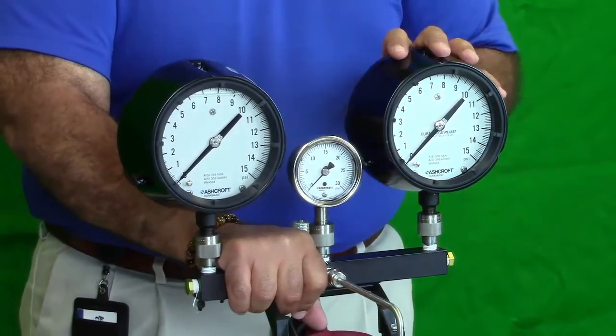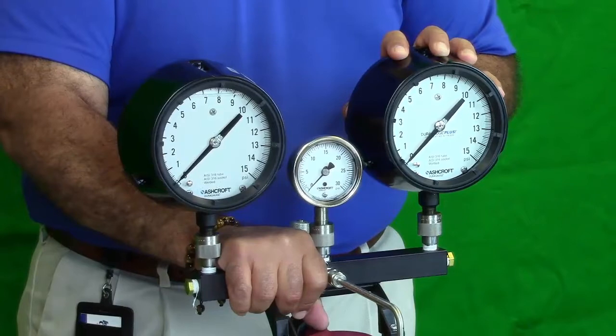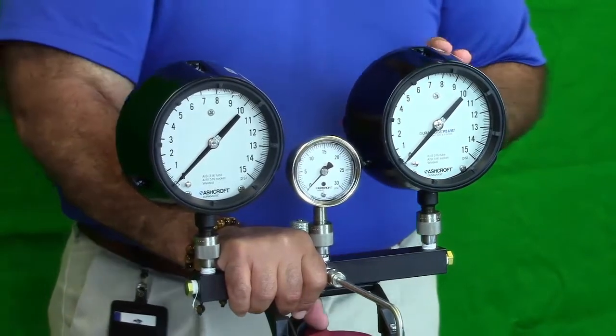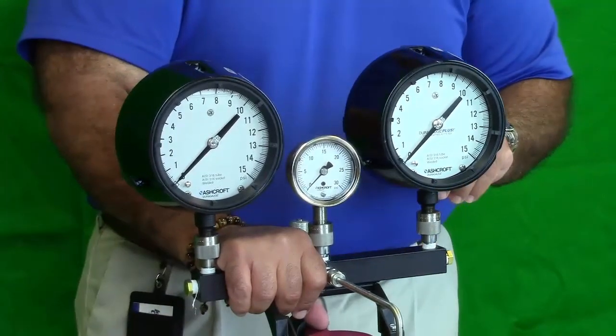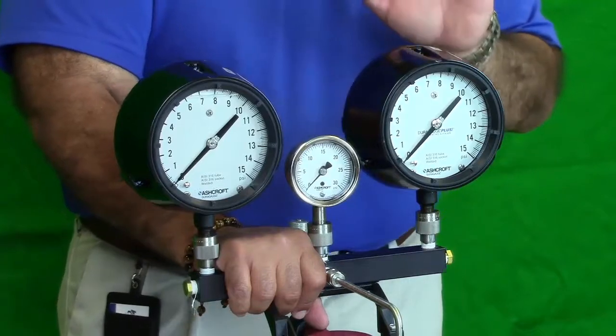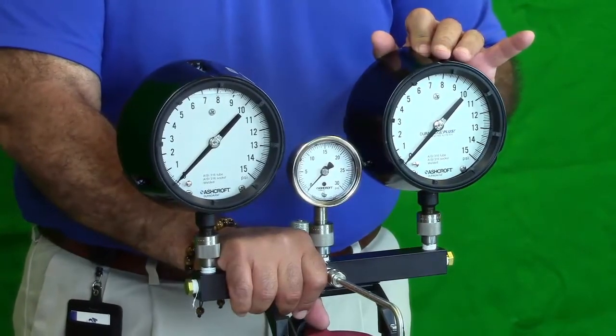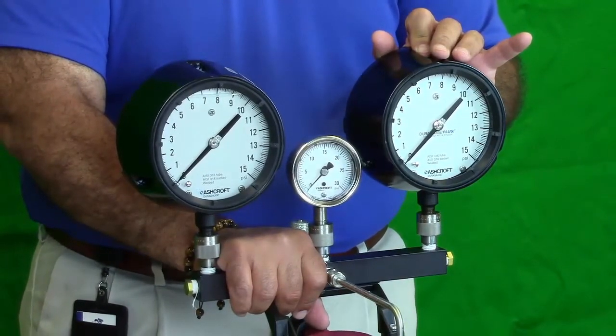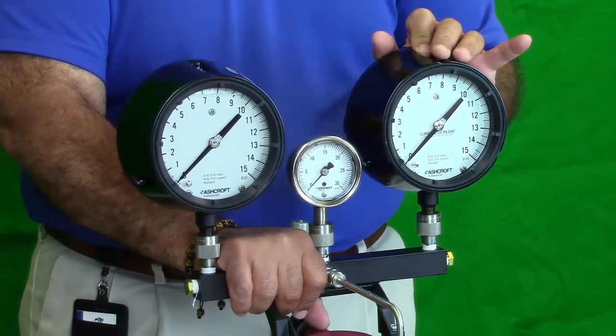Ashcroft recently introduced their Plus Series gauges, which basically uses a stabilized pinion and throttle plug, reducing or totally eliminating any vibrations that may occur on the Bourdon tube in a pulsating application.